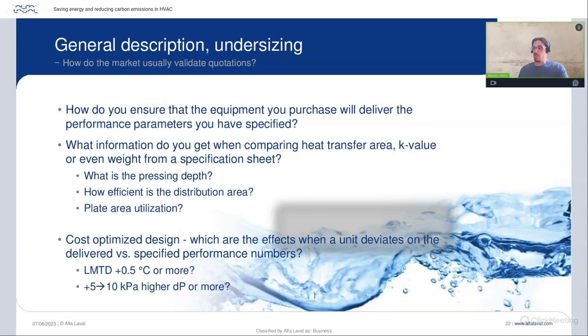And what we've seen over the last maybe 20 years is that in the HVAC industry, there has been a trend to apply something that we call a market tolerance. Basically, there is a sizing tolerance applied in the market, and it's very common that the actual unit delivered might deviate half a degree on the outlet temperatures, and the pressure drop might be 10-15 kilopascal higher than what was specified and promised in the technical specification.